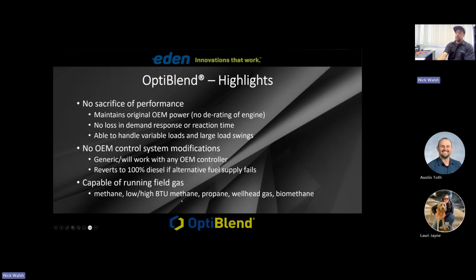This one's interesting too: running field gas. We have what we call AGC, adaptive gas correction, where if you're fracking, for instance, and pulling the natural gas out of the ground, you can essentially pump that right into our kits. I mean, you got to clean and dry it, of course, you don't want to just pump dirty gas into the kit, but pull the gas out of the ground, put it into the kit, you're fueling your own operation at that point. That's pretty awesome. And with field gas, we have no idea what's coming out of the ground. I mean, we can get a gas analysis, but who's to say you don't hit just a pocket of methane, for instance, or propane?